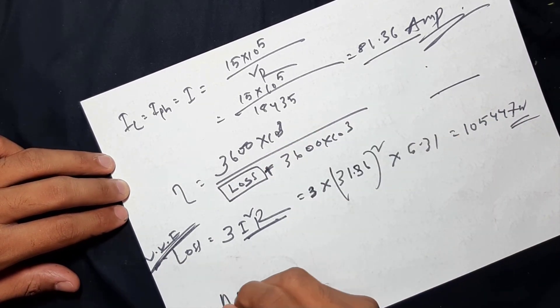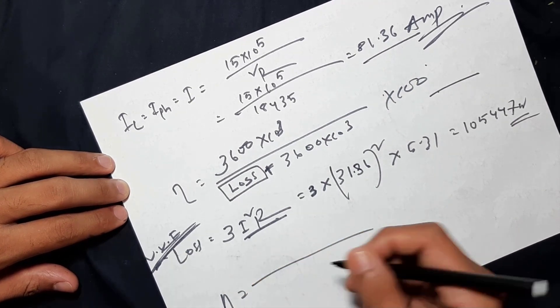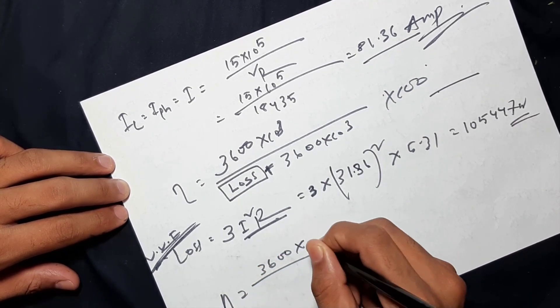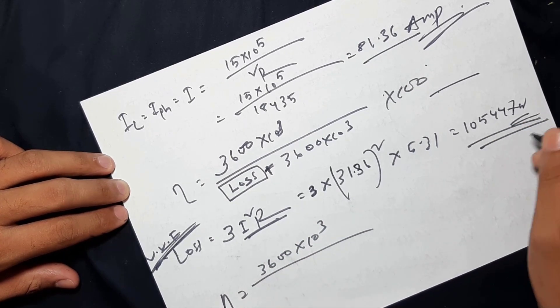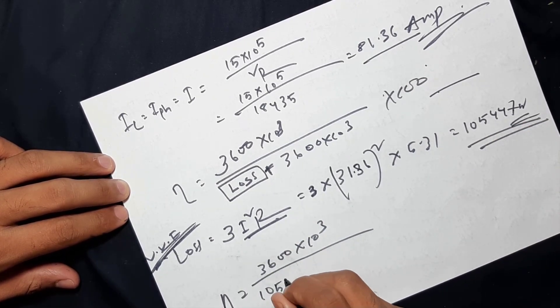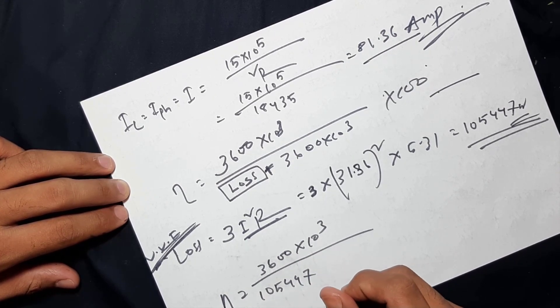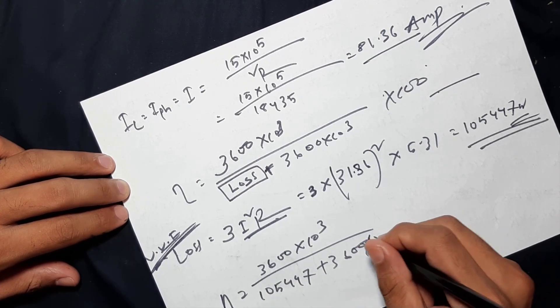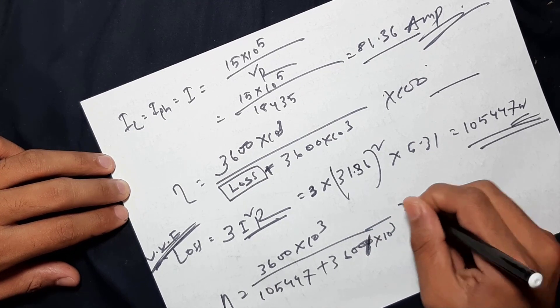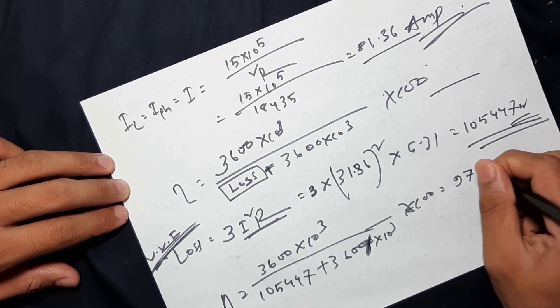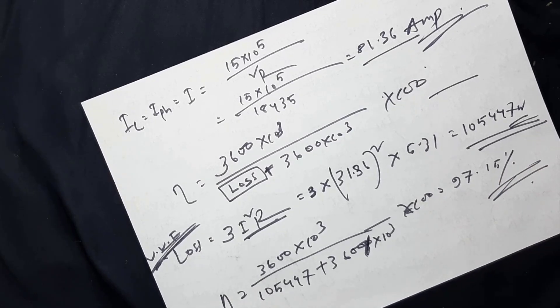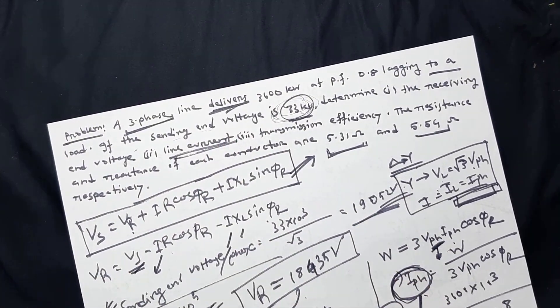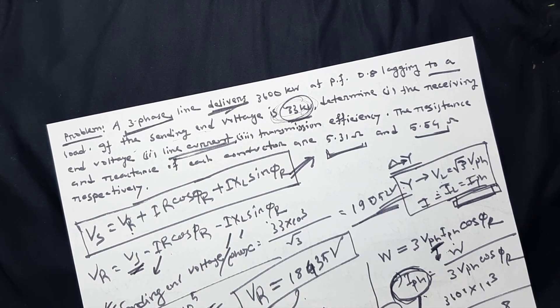So efficiency = 3,600 × 10³ divided by (loss + power delivered) = 3,600 × 10³ divided by (105447 + 3,600 × 10³). The answer is 97.15 percent. If you look at the line and phase current equation for the star connection, then you can easily solve the problem. Okay, so next time, thank you.